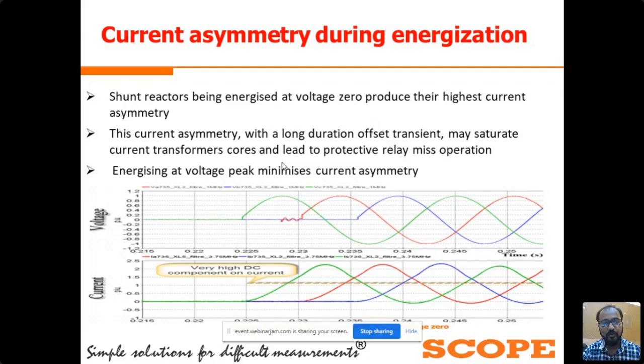After a few milliseconds it will be the same on the positive side and the negative side. But at the starting moment we have observed very high DC asymmetry. The current during random energization of the shunt reactor is near 3 to 4 times the full load current, on the positive side only or the negative side only. We have observed this type of DC asymmetry during the closing of the shunt reactor.